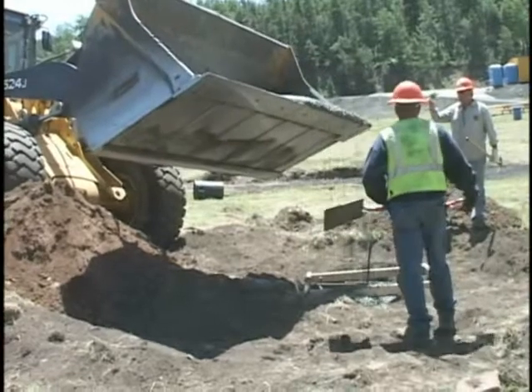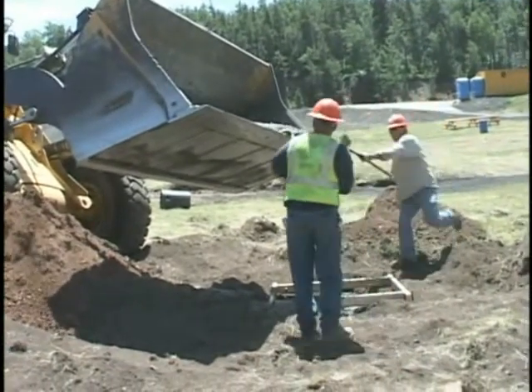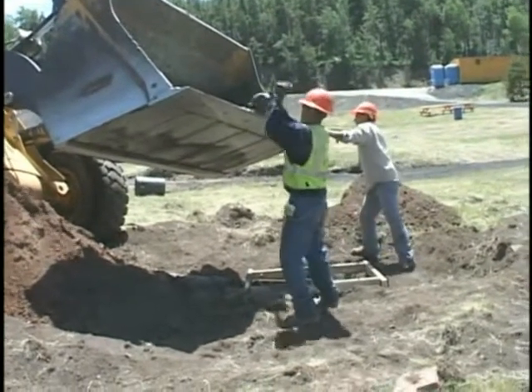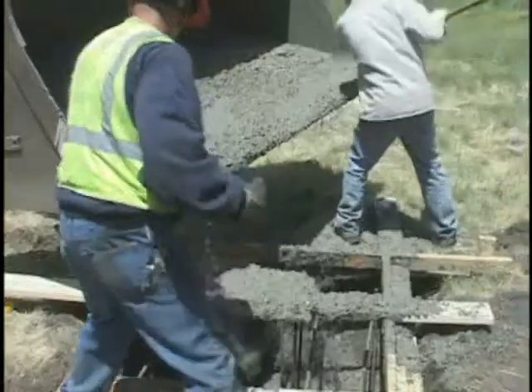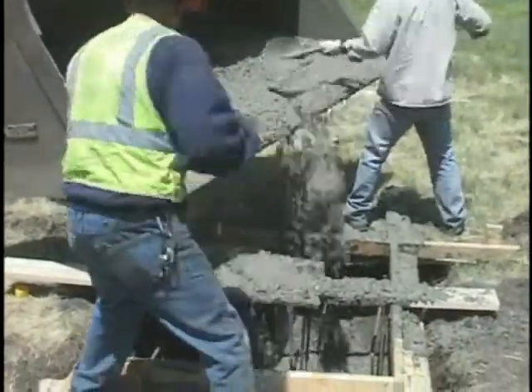It would take close to 10 yards of concrete to support our ET5, a 5,000-watt wind turbine weighing over 3,000 pounds on a 60-foot tower. The rebar placement within each pad not only holds the concrete together, but is placed in such a way as to act as grounding rods in the event of a lightning strike.